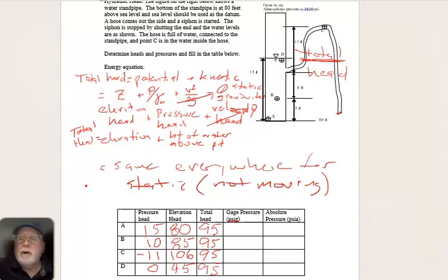If you're pulling a siphon, it can actually crush the pipe. I got into the gravity-fed water business when some people were having a problem that their pipes were crushing in a gravity-fed water system that would go over a hill. It would go downhill, then back up over a hill, it would get negative pressure, and they actually crushed the pipe. At some point, you get enough suction, or really pressure from the outside, that crushes the pipe. And before you get that, you can get air locks, and you can get vaporization of the water and stuff like that. So that's a whole thing in hydraulics, and for those of you who had hydraulics, you know about that. But I'll come back to that in just a second.